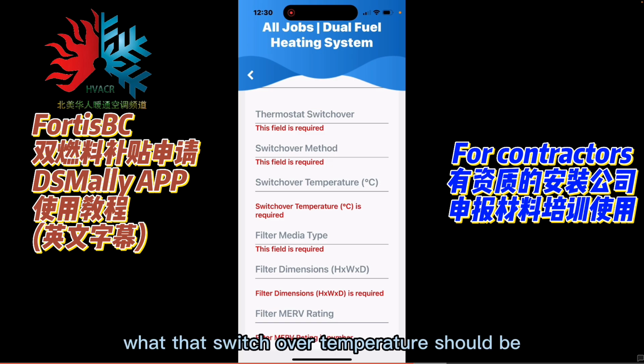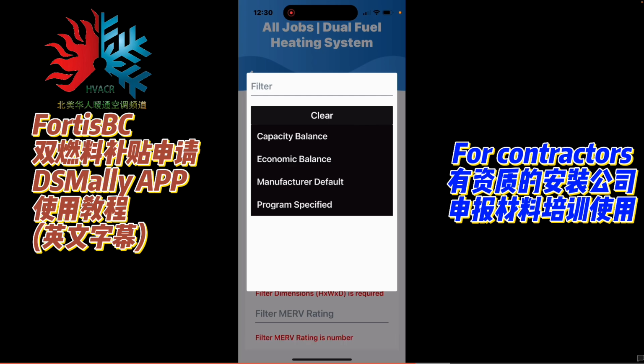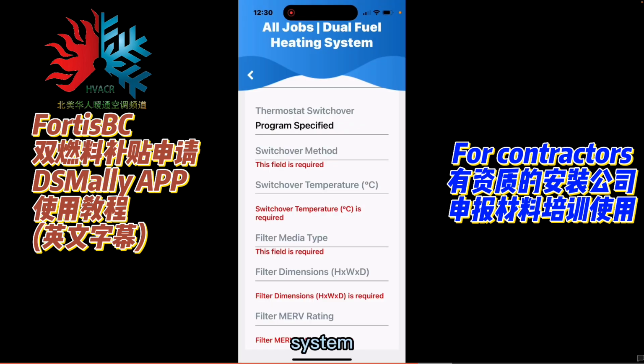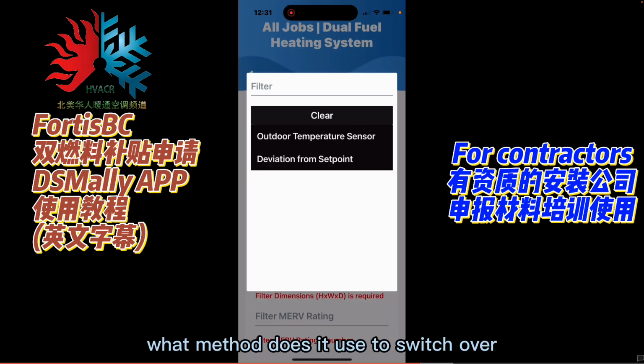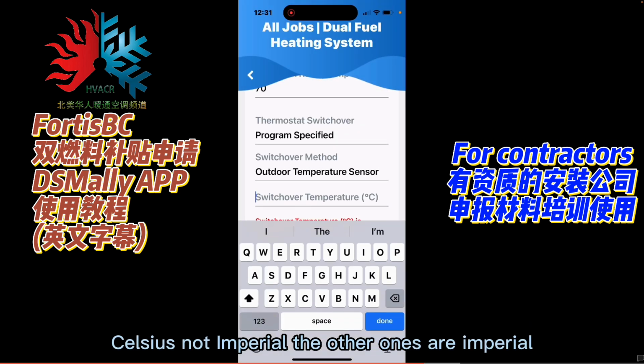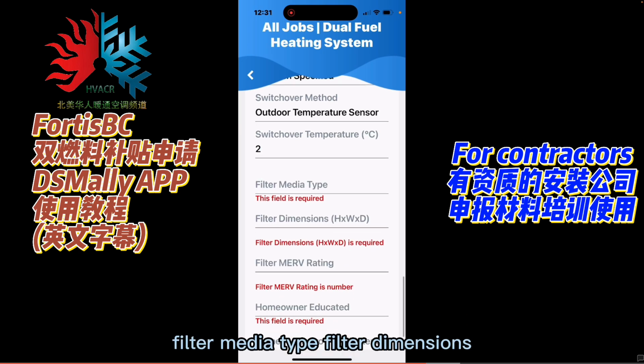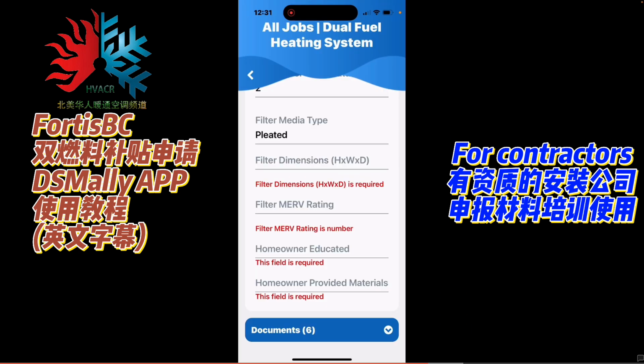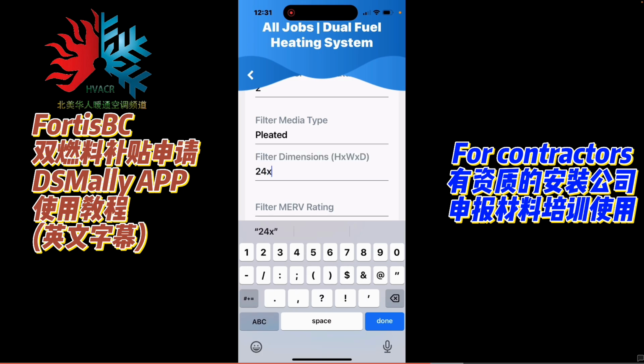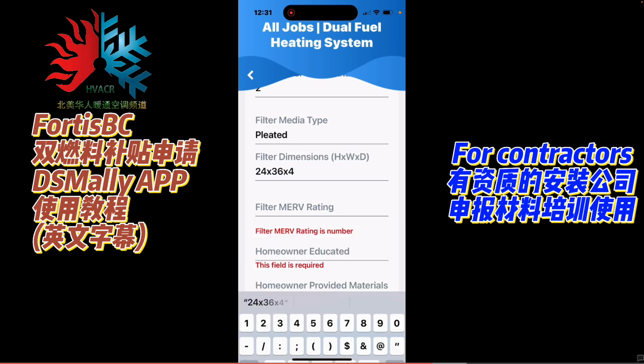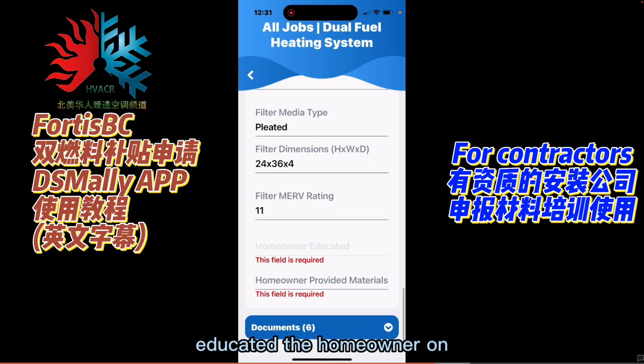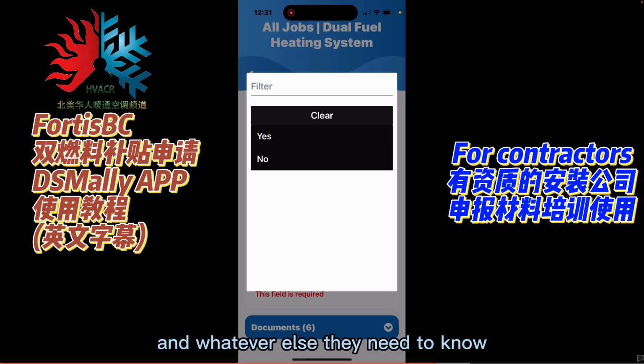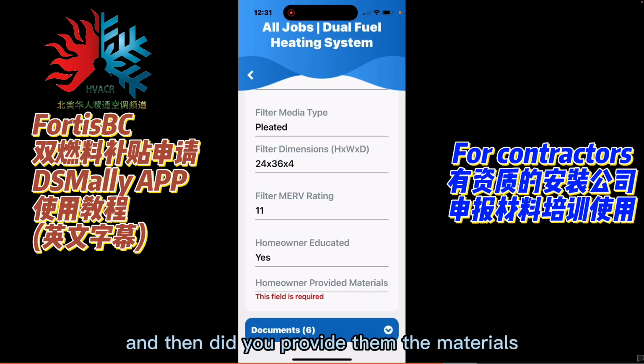And how did you determine what that switchover temperature should be? The system, what method does it use to switch over? And then the temperature. And this is in Celsius, not imperial. The other ones are imperial. Filter media type, filter dimensions, MERV rating for the filter, and then we attest that you have educated the homeowner on all your setup and whatever else they need to know about maintaining, not necessarily maintaining, but the system operation itself and the maintenance of it. And then did you provide them the materials, okay?